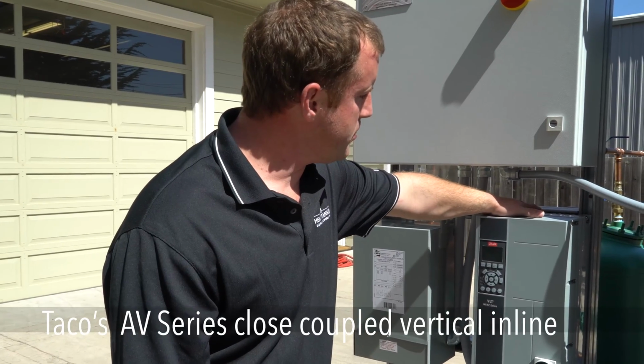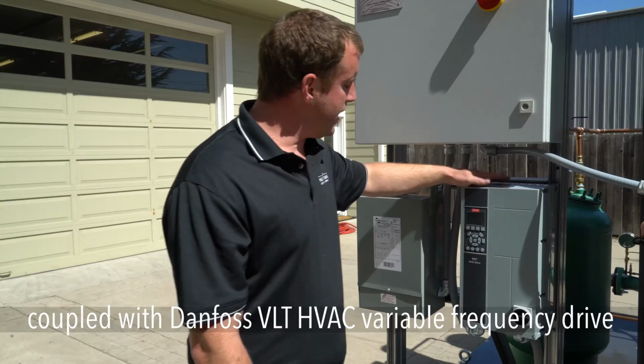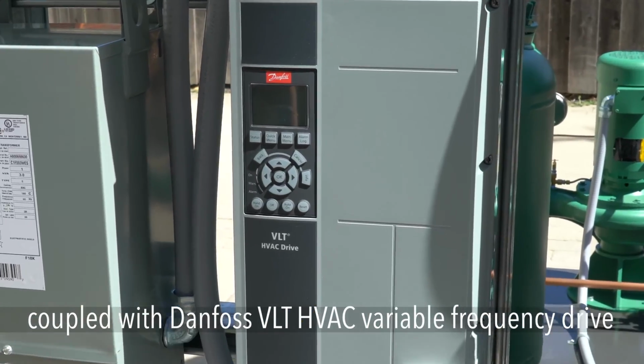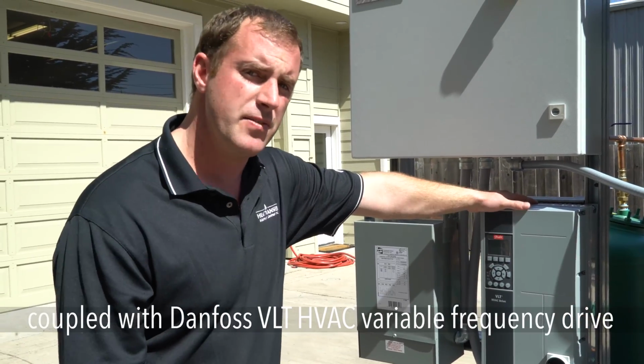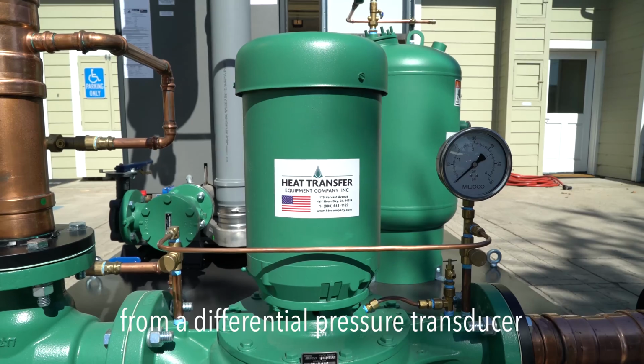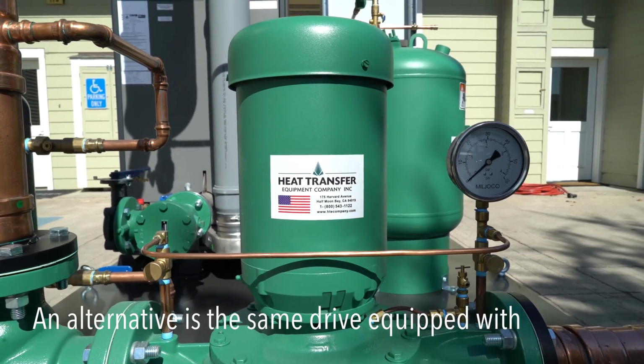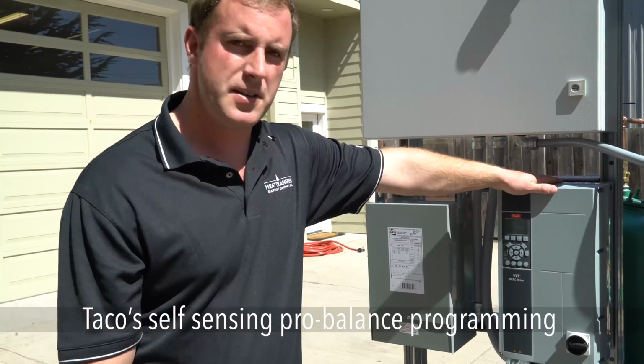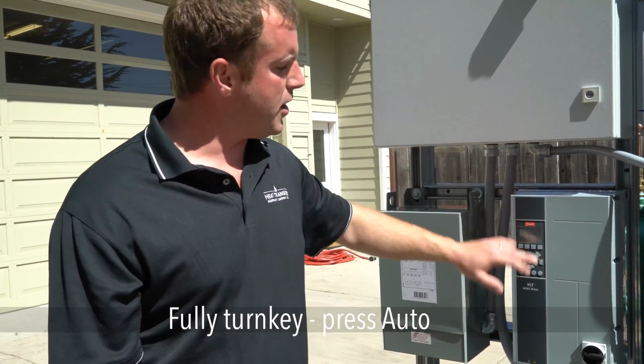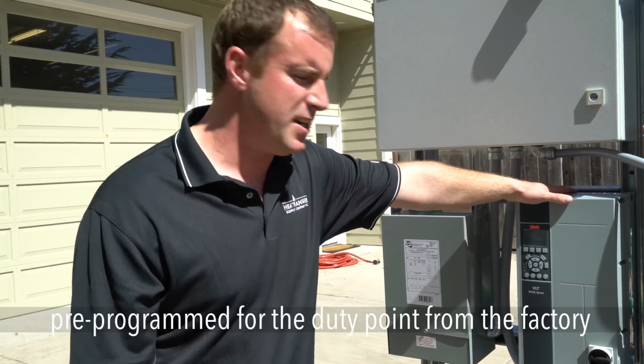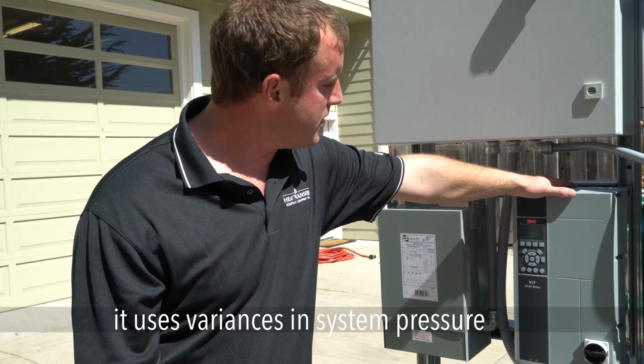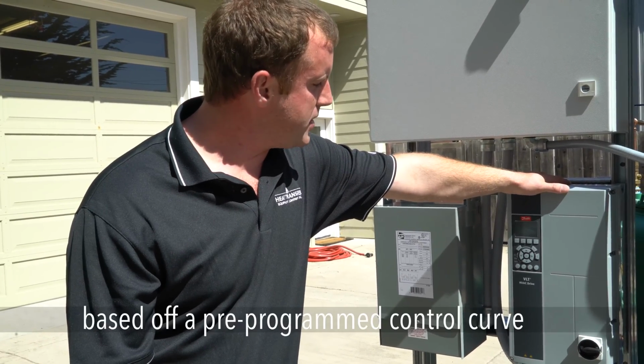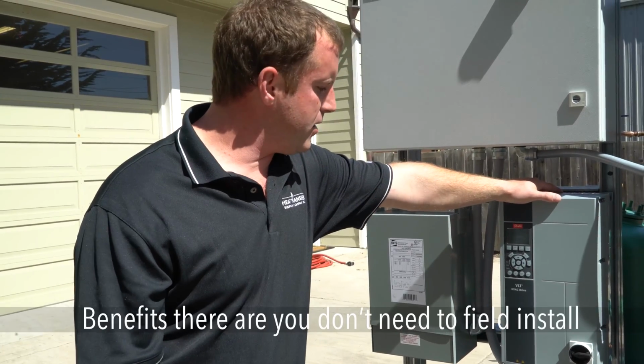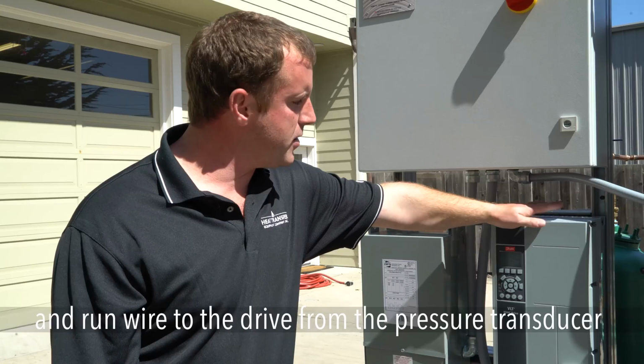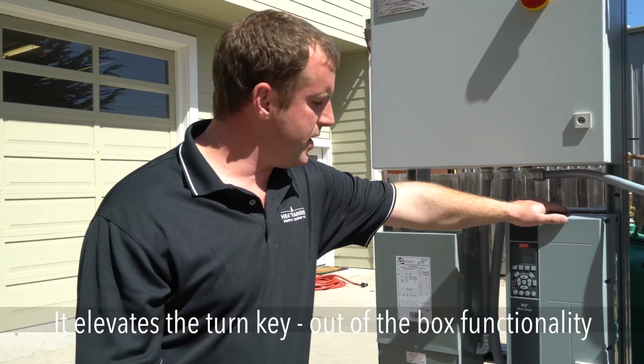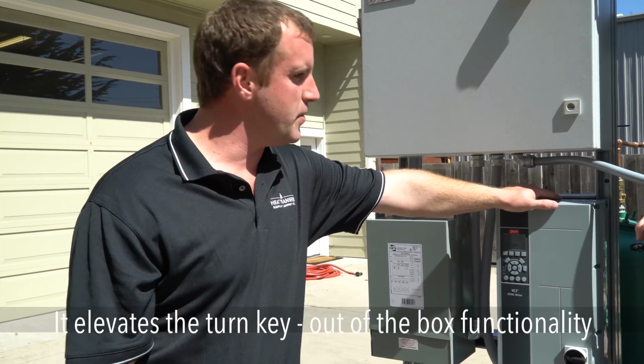Taco's AV Series close-coupled vertical inline variable speed primary pump that is coupled with this Danfoss FC102 VLT HVAC variable frequency drive. This drive requires a reference signal from a differential pressure transducer. An alternative option is the same drive equipped with Taco's self-sensing Pro Balance programming. Fully turnkey, you press auto, it's pre-programmed for the duty point from the factory, and it uses variances in system pressure detected on the motor windings to modulate the pump based off of a pre-programmed control curve. The benefits there are you don't need to field install and run wire to the drive from the pressure transducer. It elevates the turnkey out-of-the-box functionality that we offer in our package systems.